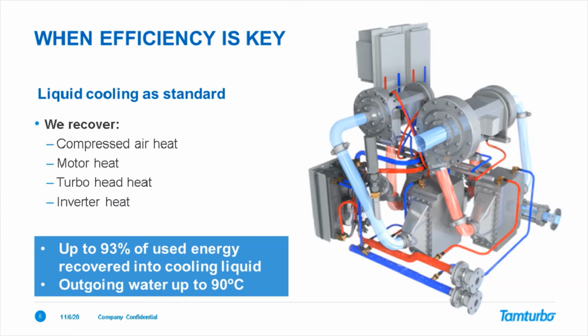So the compression is very efficient. But in addition to that, for customers who can utilize heat, water-cooled compressors have been around even for the legacy technologies for decades. But for the most cases, the amount of heat that is recovered is very low. For us, it's up to 93% of the electrical, let's say the wire energy that is taken from the electrical grid. So 93% of that we can get back in that hot water, which is in the red pipe at the bottom.